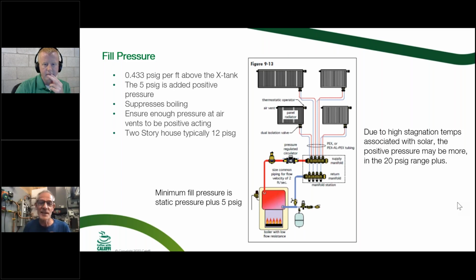So we say take the highest point in the system above the tank times 0.433. That gives you the fill pressure to get water up to the highest point. And then you add 5 pounds to that number. So as you can see here, we've got a system that's at 12 PSI on a 2-story house. Typically, that's going to give you enough. But what you need to know is that 0.433.